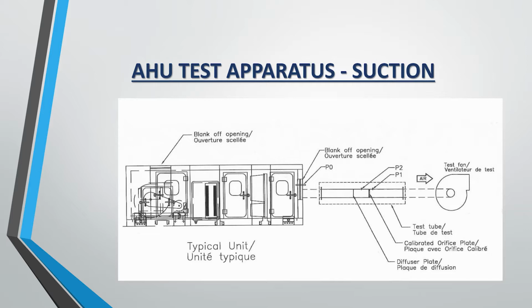This is on the suction side of a unit. So I put this in here because this is a draw-through unit. That's just a discharge here. So everything here is under suction, okay? And this was at a project at Johns Hopkins. They wanted it done under a negative.